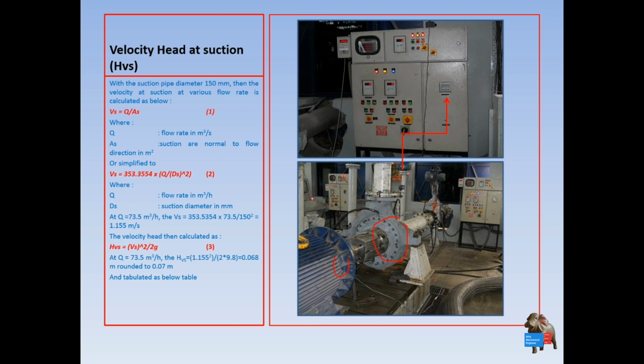I have a pressure transducer connected to this pipe at the suction, and then I also have a pressure transducer around here, connected to this pipe. Let's say you go for the next flow capacity. Let's say in this example the flow capacity is 73.5 meter cubic per hour.